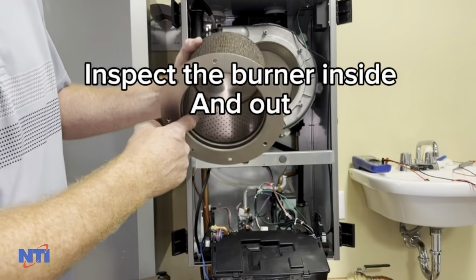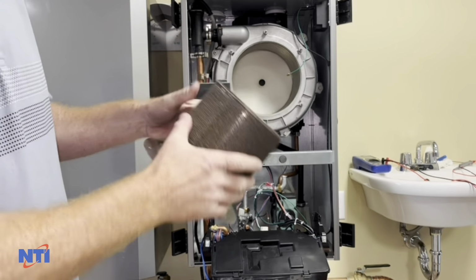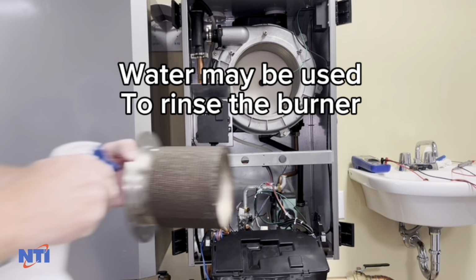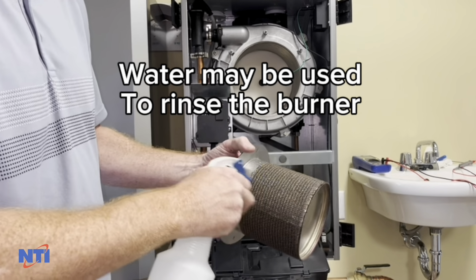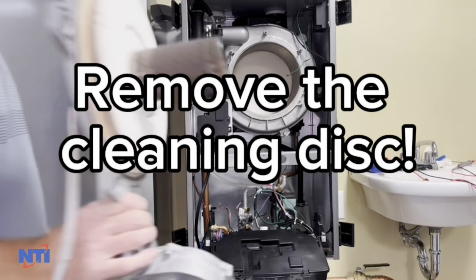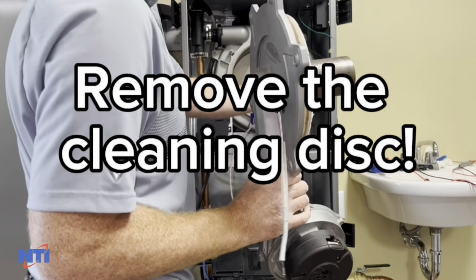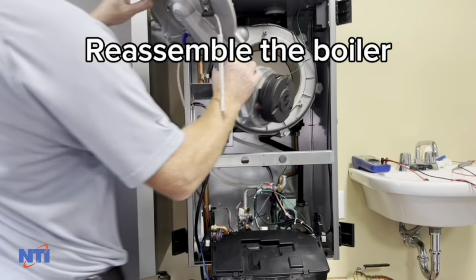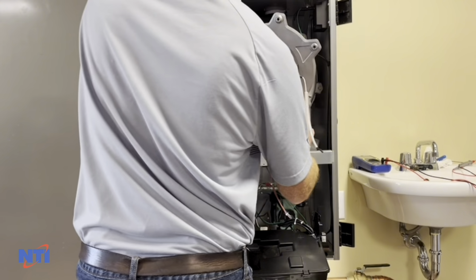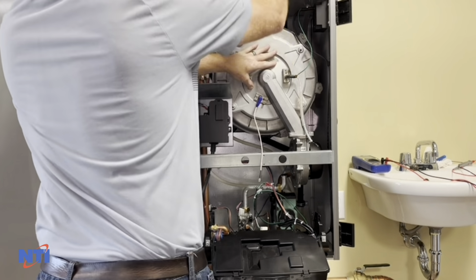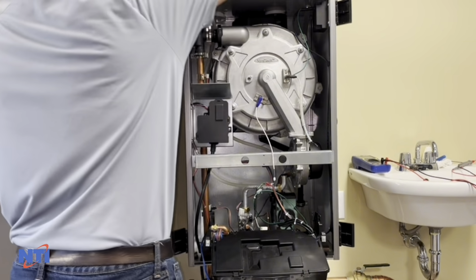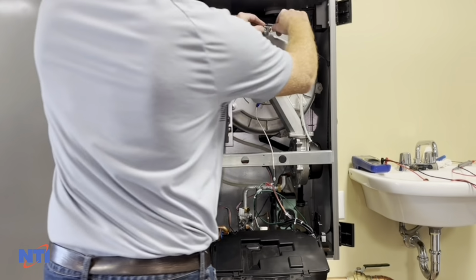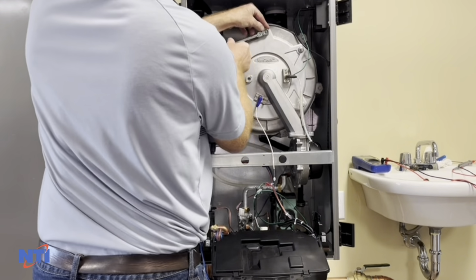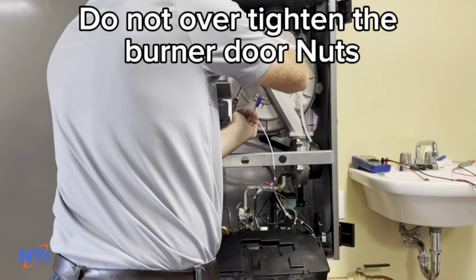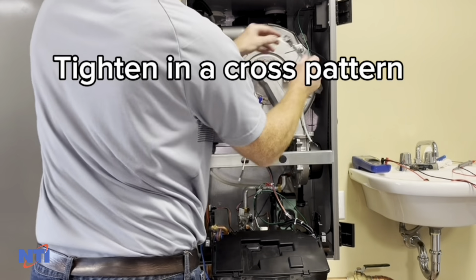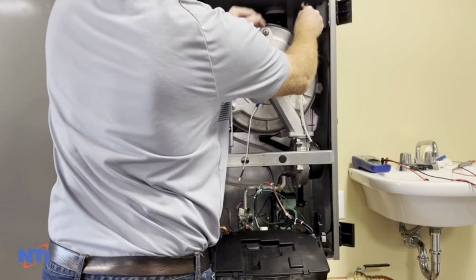If it is suspected that the burner is dirty, the burner may be cleaned by vacuuming it out and rinsing it thoroughly with water. This procedure should be done every 2 or 3 services to ensure the burner is in good condition. Before reassembling the boiler, ensure the cleaning disc is removed. Once the boiler is fully assembled, perform a combustion test. Use care not to over-tighten the burner door nuts. They require no more than 5 pound-feet to torque properly.